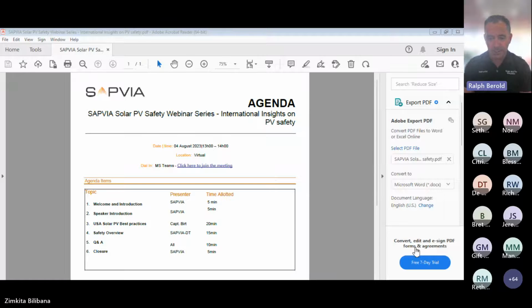The other part was, we said life safety, because that's one of the critical parts of this. The industry's working to put this on roofs. And we said, how do we keep the people who are working with this stuff safe? This is live right there. Well, if you look at 230, 50 hertz, we tell the industry this from our tests. If you take 50 hertz, you've got 100 chances per second to let go of that power. Now, with high voltage DC, you don't, you have zero. So what you're looking at is a complete shift and change in the safety aspect, not just in fire, but in life safety.